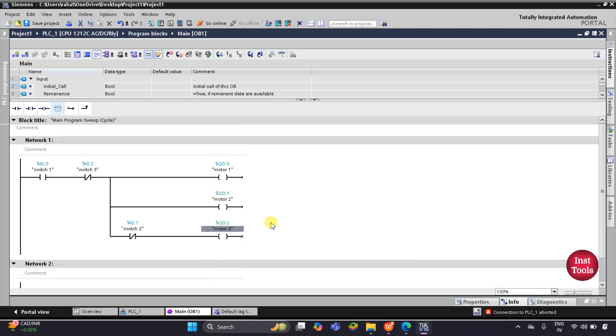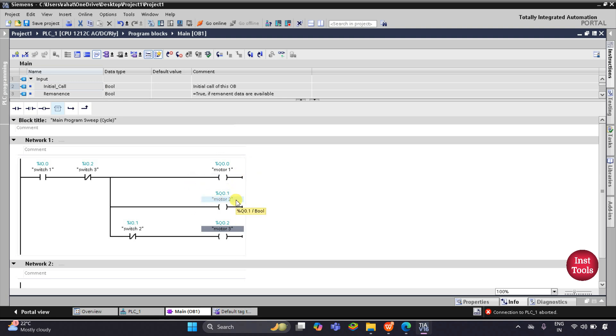When switch 1 is turned on, current will flow through it and motor 1, motor 2, and motor 3 will turn on. Switch 3 and switch 2 are used as normally close contacts — in their default state they allow current to flow through. When switch 2 is turned on, it will not allow current to flow, so motor 3 turns off, but motor 1 and motor 2 remain on. When switch 3 is turned on, its normally close contact blocks current and all motors — motor 1, motor 2, and motor 3 — turn off.